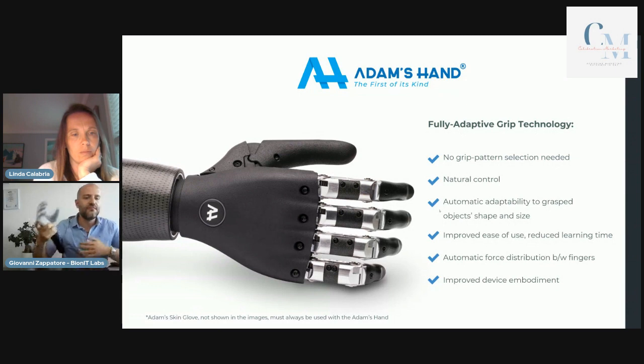Adam's thumb is manual, but it's not a standard friction. So you cannot move it by simply trying to rotate it. You have to push and then I'm going to hide this for a second so we can see you better. So you have to push and then you can rotate. When it's in place, it's really stable, so heavy objects do not risk moving the thumb inadvertently. While when it's up, it's really easy to move it, so you don't risk rotating the hand instead of moving the thumb. So it's not a standard friction mechanism, and this makes it more user-friendly for sure.